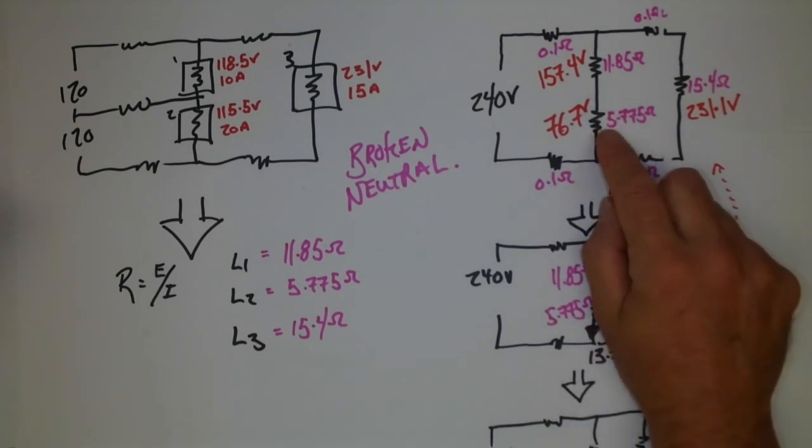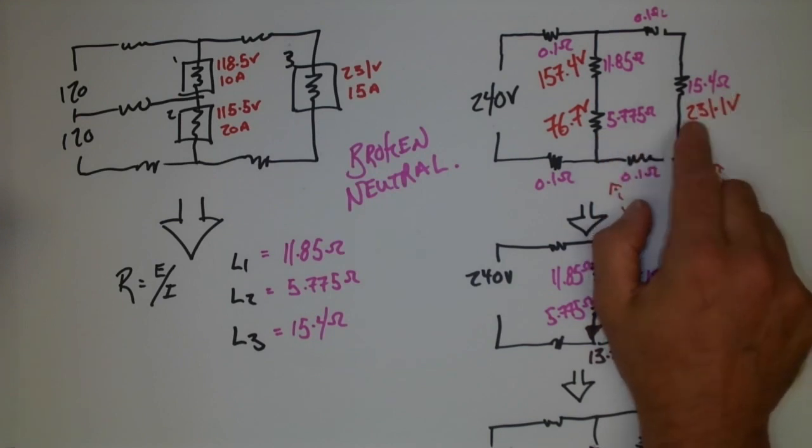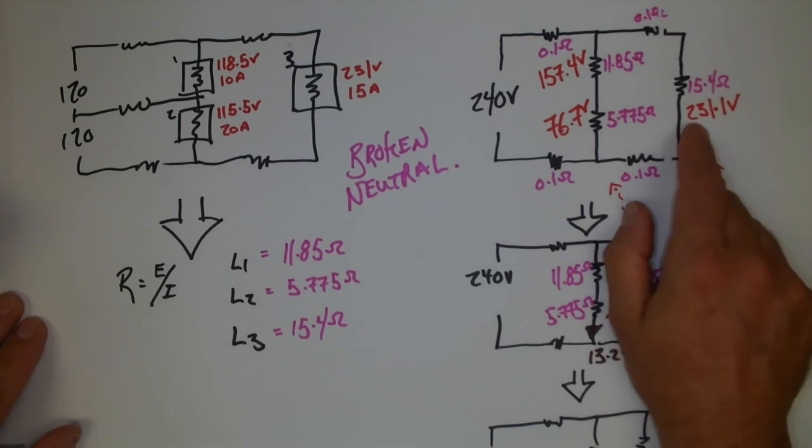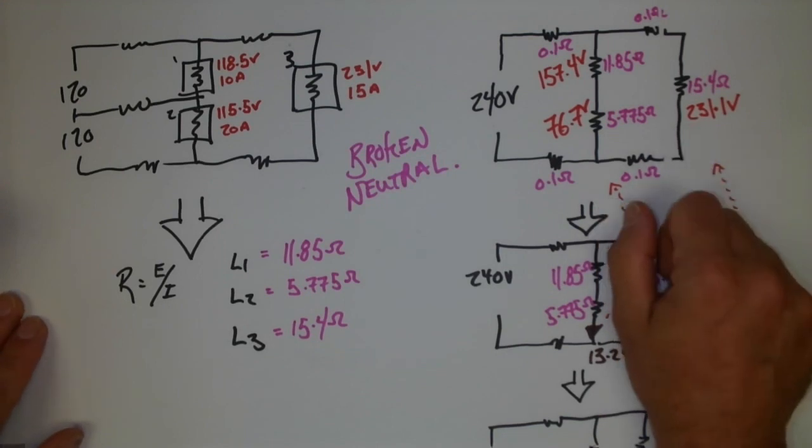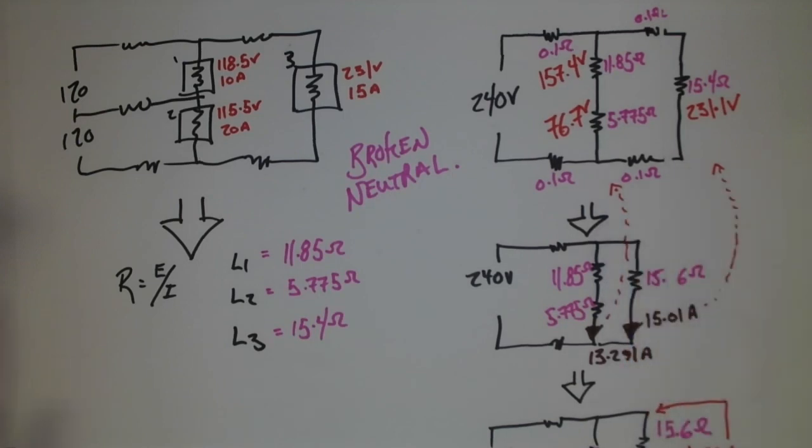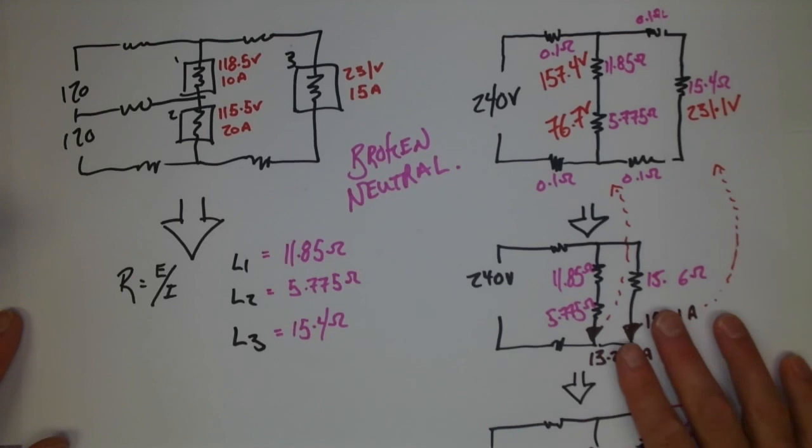This down here, well, this one is under voltage, so not much will happen. Whatever it is will cease to operate or be dimly lit. And then finally, what about the 240 volt load, or the load that was rated for the full 240 volts of my single phase system? Well, you'll notice the voltage didn't change too much there, did it? The voltage remained pretty much untouched. And so the 240 volt load would continue to operate.